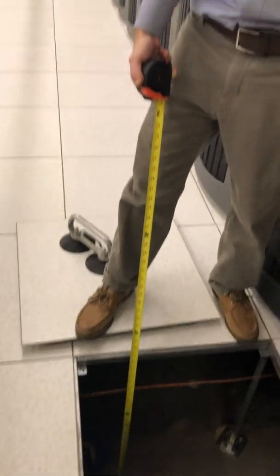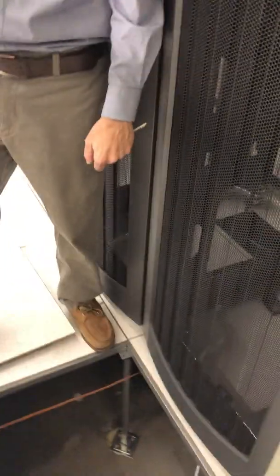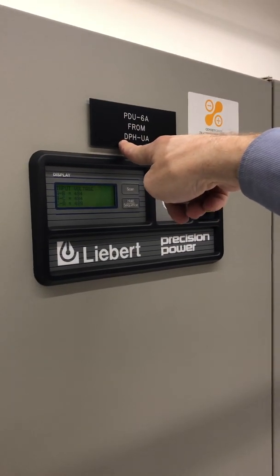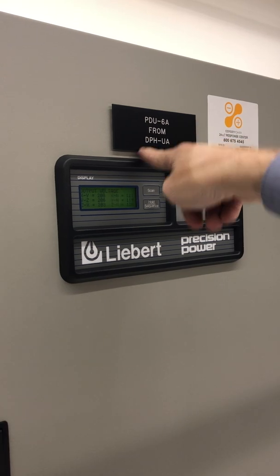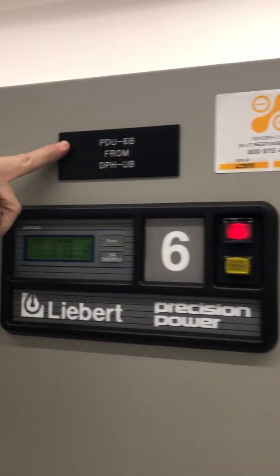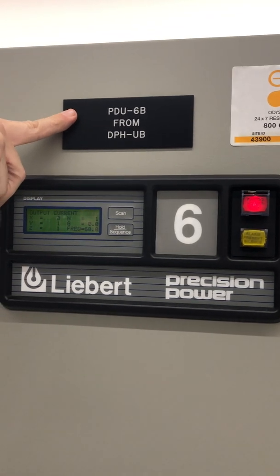Do you have hot and cool aisles? Ultimately, yes. Hot and cool aisles. The IT department also had some extra money, so they bought some extra 2-post racks and some extra 4-post traditional cabinets. Racks are already here. So, as you can see around the perimeter of the room, some of the power is in place already. So as you see, this is the head end of the feed from UPS room A and battery room A, and then it's mirrored from UPS B and electric room B.